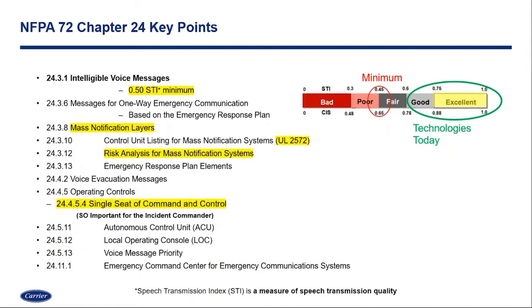Digging into NFPA Chapter 24 of 72 a little more — recall that code is the minimum requirement, what can be minimally enforced. We can always do more than code requires, but we can't do anything less. With NFPA 2018 being more and more widely adopted throughout the states as more jurisdictions bring in newer releases, we're going to see a lot of these points enforced throughout your communities. When we look at intelligibility, it is going to be one of those key factors — the STI or CIS scale, the speech transmission index. That's essentially how clear the message is.